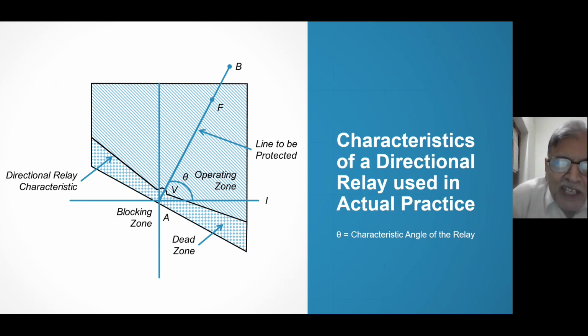the zero torque characteristic is what? When voltage is zero. Voltage is zero torque characteristic. So you can see that line, slant line, zero torque line. I will show by my cursor. This is a zero torque line. But this is not a characteristic because at voltage zero relay will never operate. You will need some minimum voltage, and this minimum voltage in electromechanical relay may be large. In static relay it may be 10% or 20% of that. In numerical relay it may be yet smaller, but at zero voltage no relay will operate.